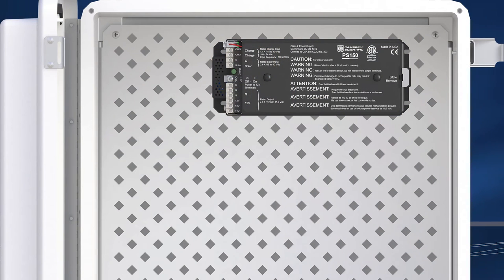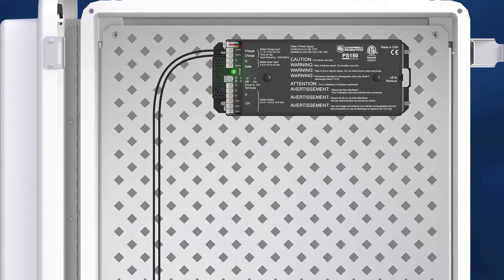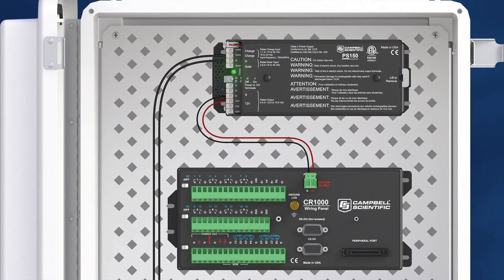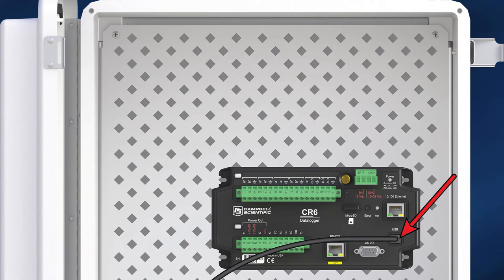I have a PS150, and while we're in the office, it's being trickle charged from AC power. The flashing green light indicates the battery is being charged. The datalogger's green power connector is wired to the power supply's 12-volt and ground terminals. Make sure the power switch is flipped to the on position. Alternately, with a CR6, I could provide temporary power just using the USB cable.